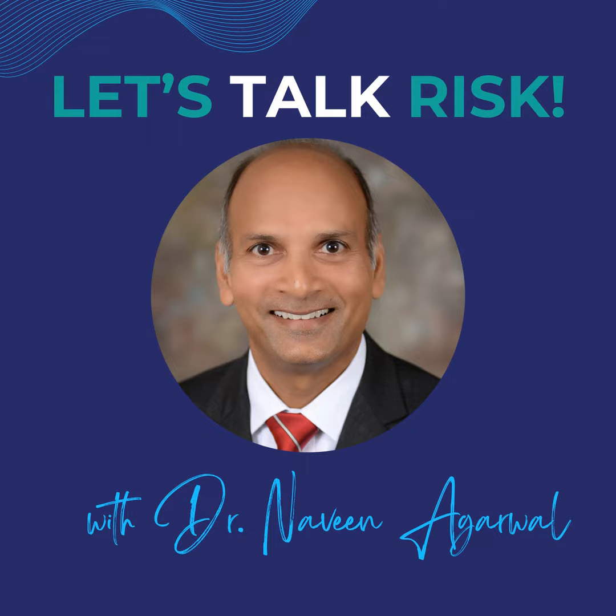So the way I always think about it is there's usually a sequence of events that occur within the software. And then before you get to the patient being harmed, there's additional events that occur more in the clinical environment around how the clinician's interpreting information or the actions they're taking on it. And so I think it's very clear that for the events occurring within the software and failure modes occurring in the software, you say the probability is 1. But for all the events that are occurring outside, which is often encompassed in the P2 probability, that will not usually be 1. Because if you don't account for that, you end up with a situation that's not good, because then you're having to treat every software vulnerability at the highest level, which isn't practical and kind of misallocates resources. I don't know.